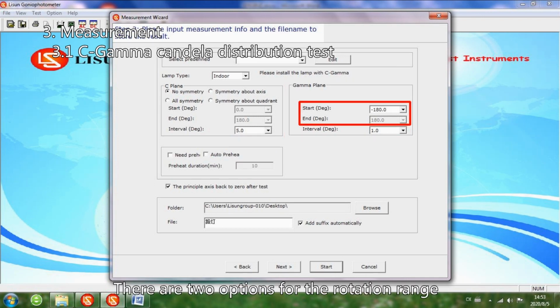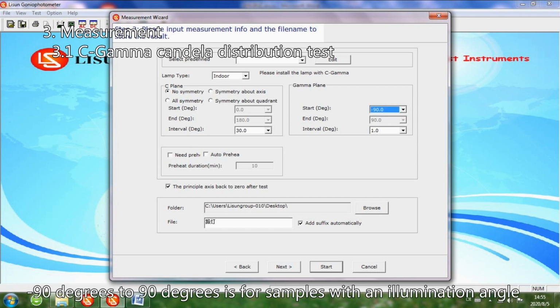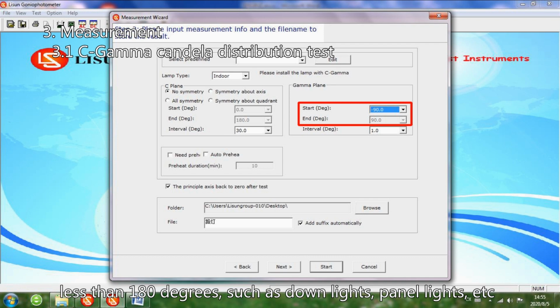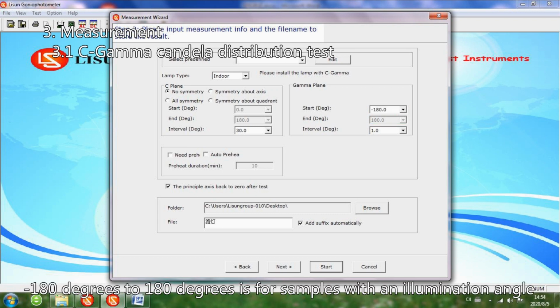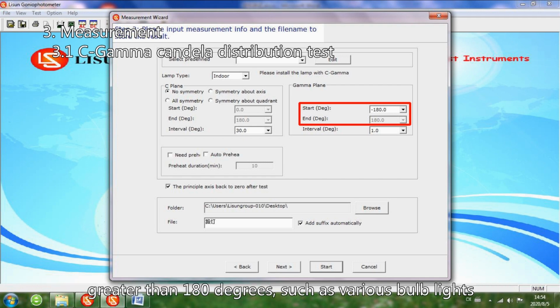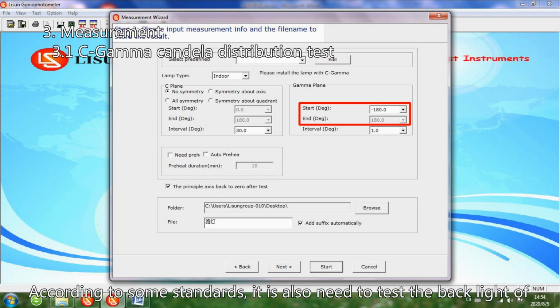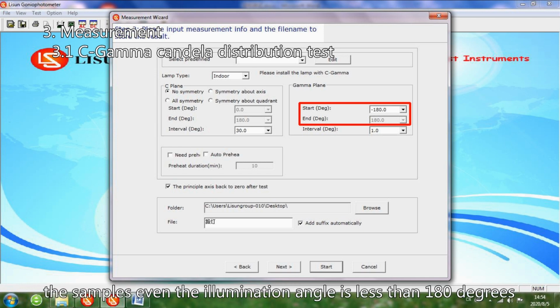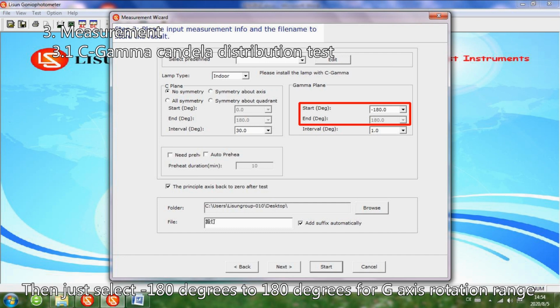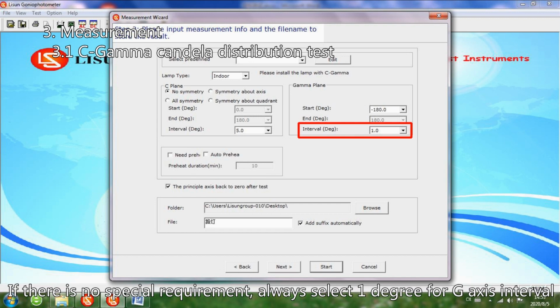G-plane. There are two options for the rotation range. -90 degrees to 90 degrees is for samples with an illumination angle less than 180 degrees, such as down lights, panel lights, etc. -180 degrees to 180 degrees is for samples with an illumination angle greater than 180 degrees, such as various bulb lights. According to some standards, it is also necessary to test the backlight of the samples even if the illumination angle is less than 180 degrees. Then just select -180 degrees to 180 degrees for G-axis rotation range. If there is no special requirement, always select 1 degree for G-axis interval.